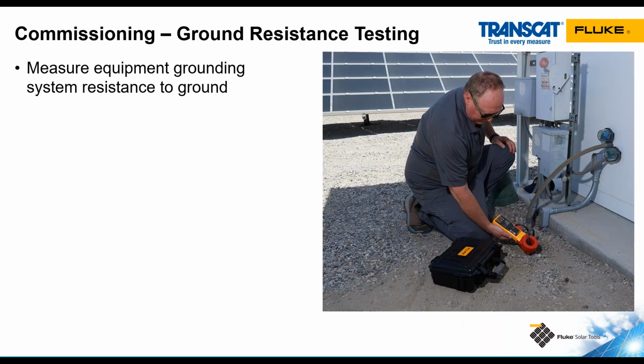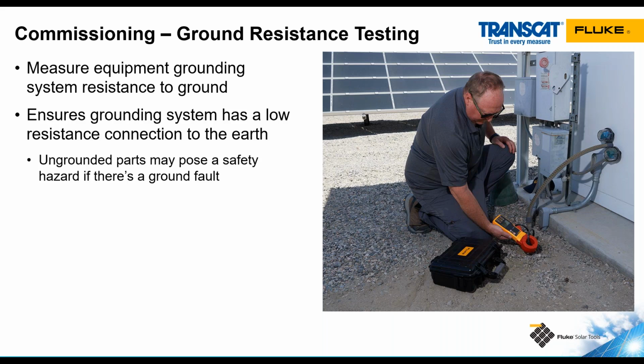A related test is making sure that our ground rod actually has a good connection to the physical earth. There are several different tests we can do this. We're doing it for the same reason. We're testing our bonding between metal parts to make sure that there is a good path to ground. If we don't have good bonding, another issue we can run into is that overcurrent protection devices like circuit breakers may not work because they need that loop path to ground for that current to go through the ground into the breaker and trip the breaker.